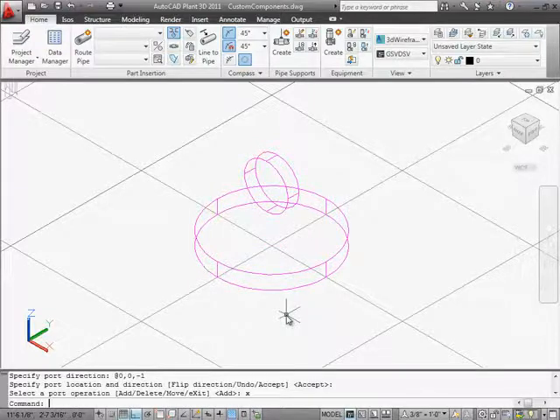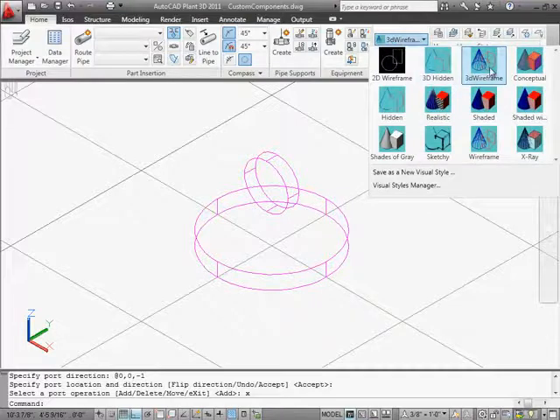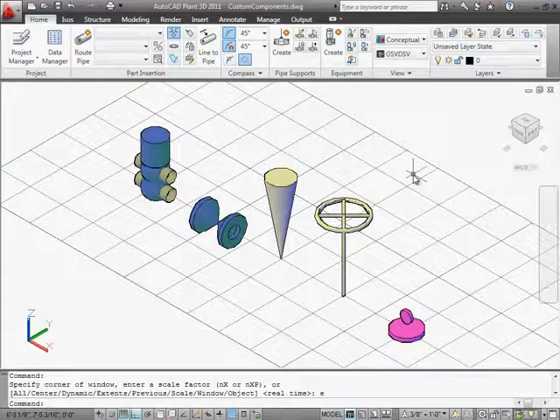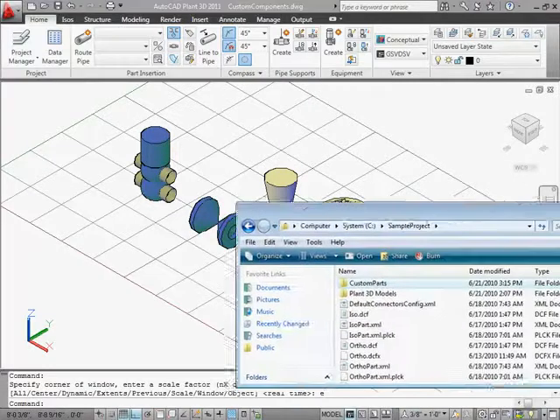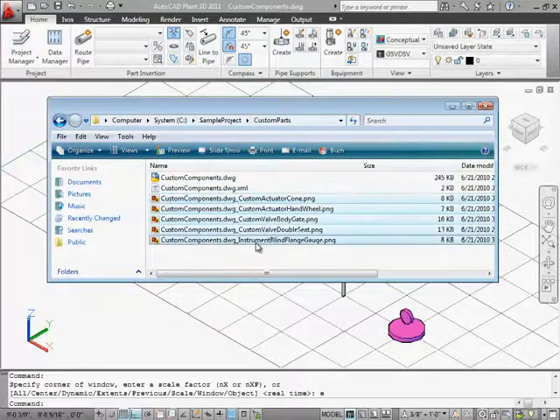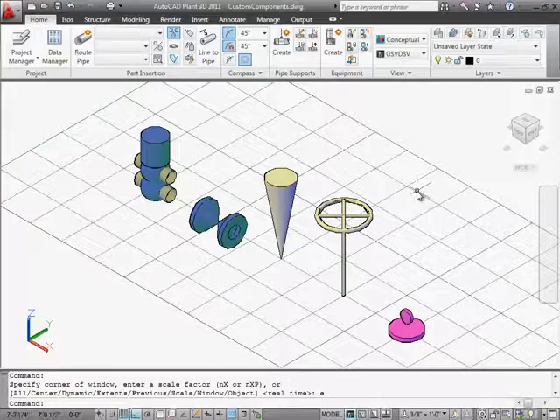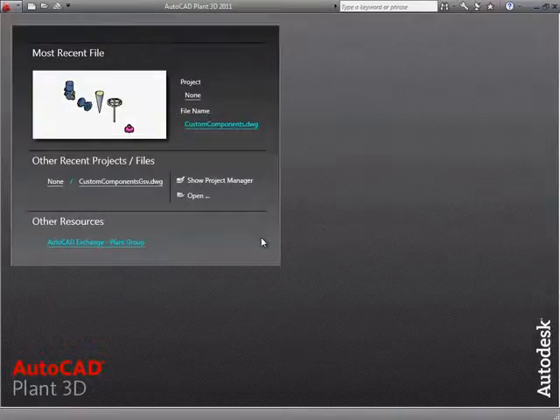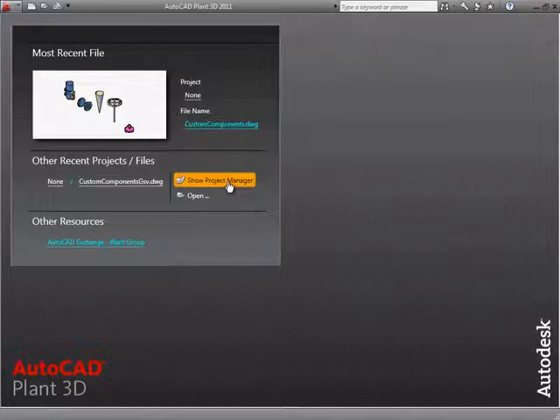I'm going to restore the view and zoom out, and we're done adding ports with plant part convert. Before we start using these blocks in AutoCAD Plant 3D, let's take a look at some of the files we created. In this custom parts folder, we have the original drawing, an XML file identifying what's available in the drawing, and a bunch of PNG preview images. If you want to share or move your converted blocks, you need to include the XML and PNG files along with the DWG. We can now save and close this block file.